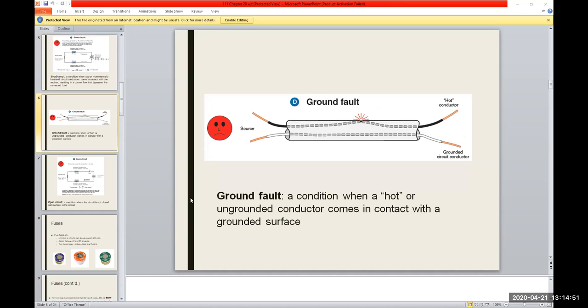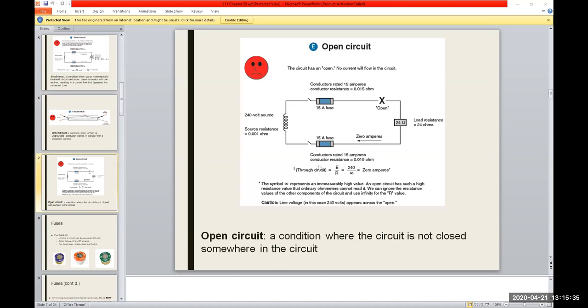And that's when we get into something like this. For that kind of situation, you'd have to have something that can sense that and be a little smarter than the average circuit breaker or fuse. A circuit breaker and a fuse are what they call a passive device. There's nothing really in there. It's all basically mechanics. It's just a reaction, like in the case of a fuse where the filament will burn out if the current becomes too much for that filament. And a circuit breaker has that little coil inside, and it just reacts. But when we get into something like a ground fault, we need it to sense that and trip right away, because otherwise we could have a fire hazard.